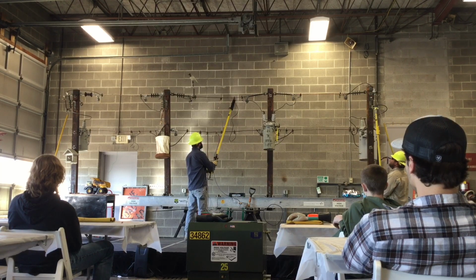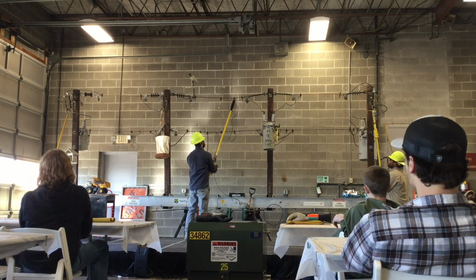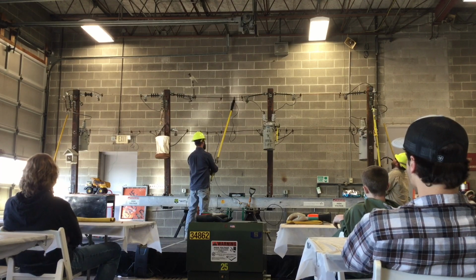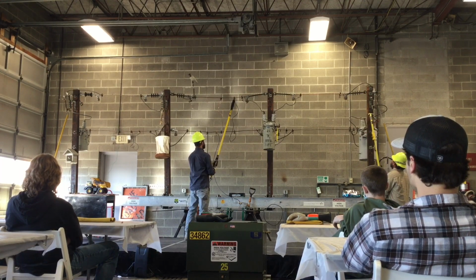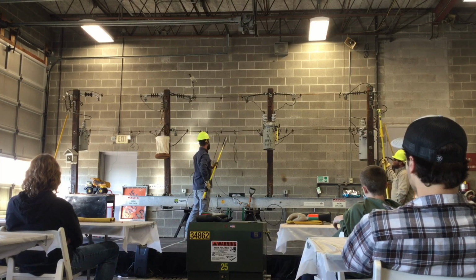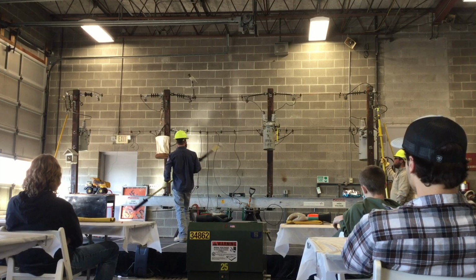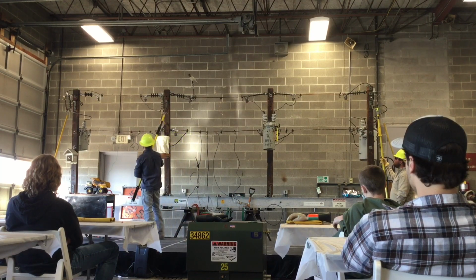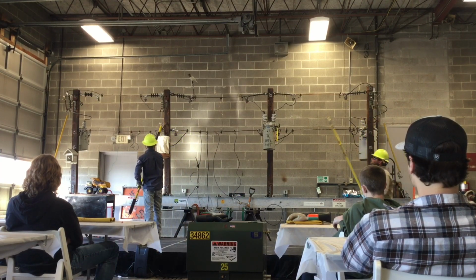So we also use these breakers. We call it a one-shot. Anytime we're going to go work on the line energized and glove, we'll put the breaker on one shot, to where if there's a fault, let's say we're working on the line and something happens that shouldn't happen, and there's a fault, that breaker will open and it will not reclose back in on us, okay?